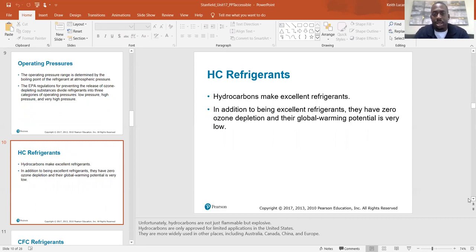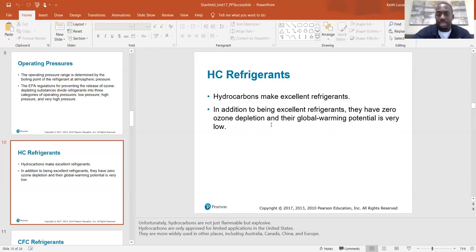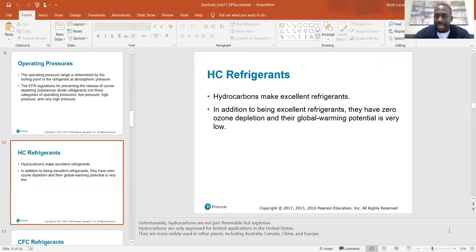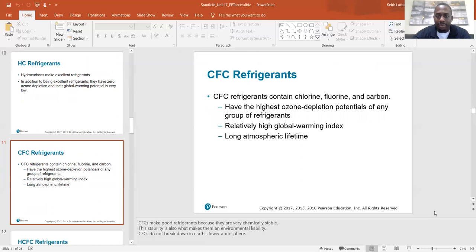HC refrigerants — hydrocarbons — make excellent refrigerants. In addition, they have zero ozone depletion and very low global warming potential. ODP, or ozone depletion potential, is something you'll see a lot. HC refrigerants have the lowest ozone depletion potential because they don't contain any chlorine, which is what damages the ozone. Unfortunately, hydrocarbons are not just flammable but explosive, and they are only approved for limited applications in the United States. They are more widely used in Australia, Canada, China, and Europe. Propane, for example, is used as a refrigerant in some places, but it is dangerous.